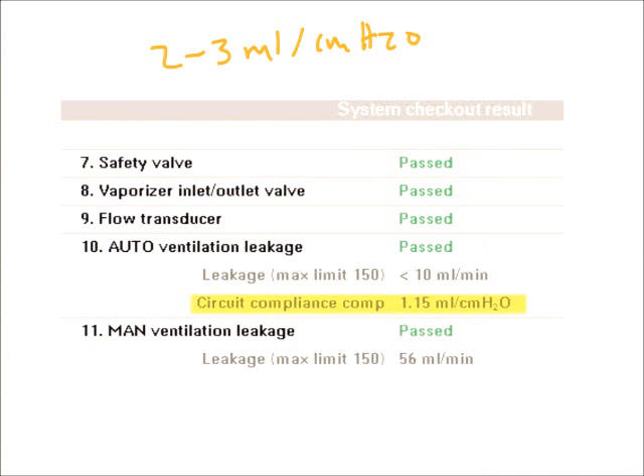And what this means is, basically, we can think of this for every centimeter of water above your set PEEP, you're going to lose 2 to 3 milliliters of tidal volume. Or in this case, based on the circuit compliance, you're going to lose 1.15 milliliters.